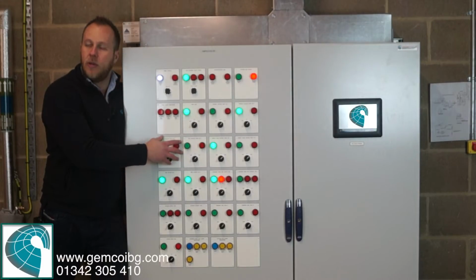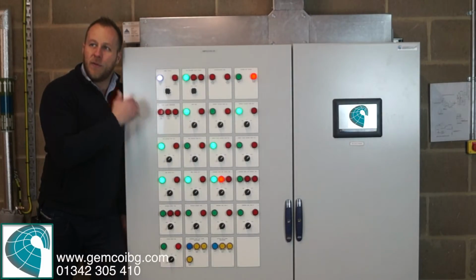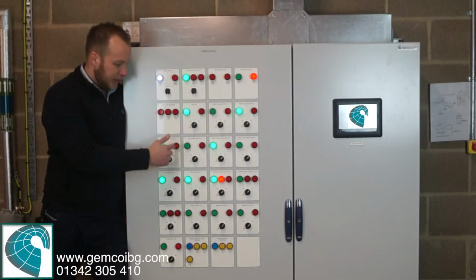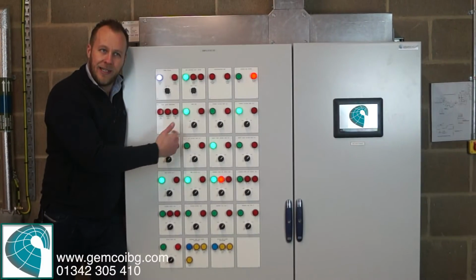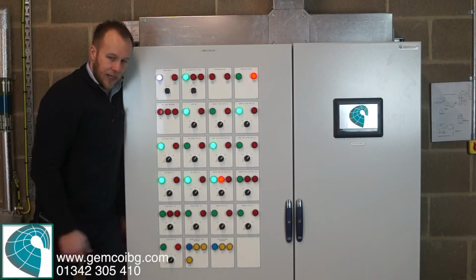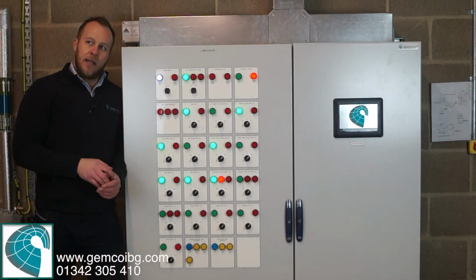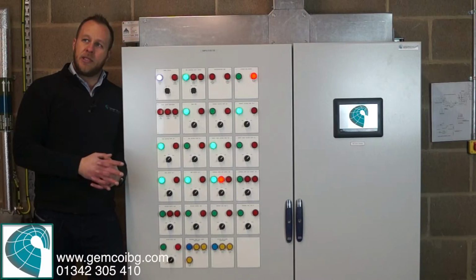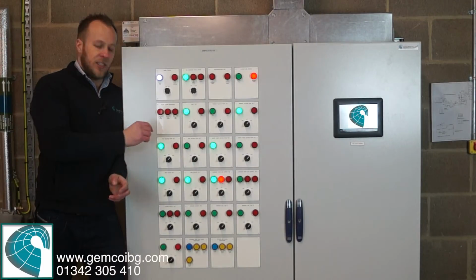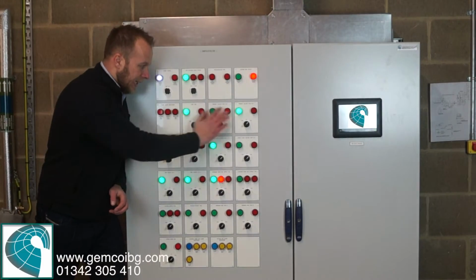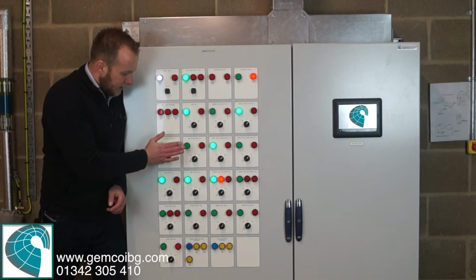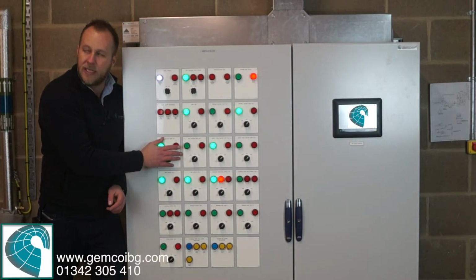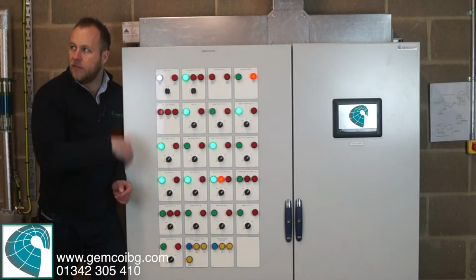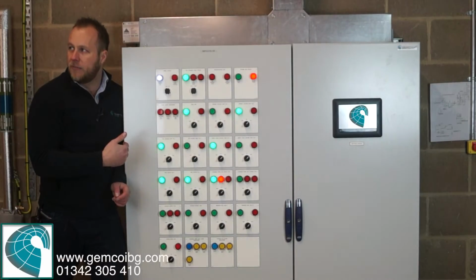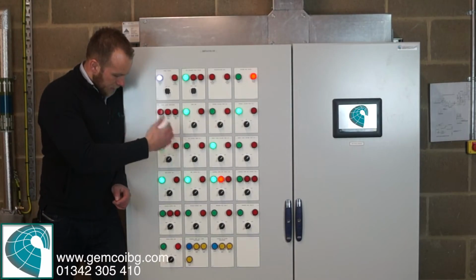The reason there's 2 is because for maintenance purposes and wear and tear, we change the duty of the pumps weekly so that you get equal use out of each pump. And another reason we put 2 pumps is because once the duty pump is enabled, so every Monday morning you'll have a duty pump. Say one's running, that's the duty pump for that week. Next Monday we'll change over to pump 2, and then the next Monday it'll change back to pump 1. So that saves the wear and tear on the pumps.